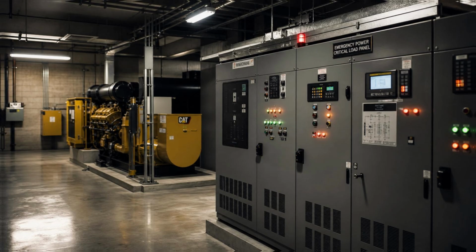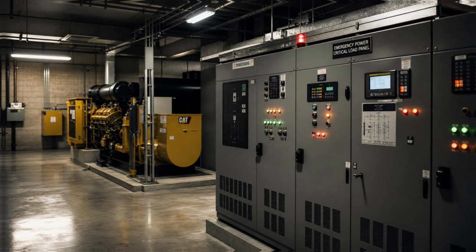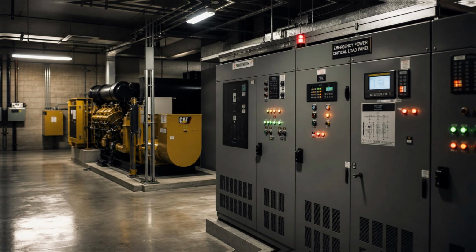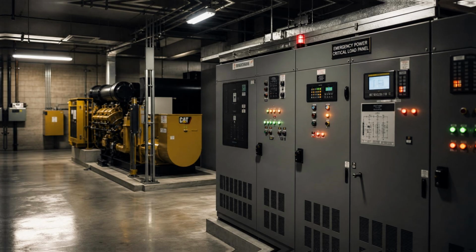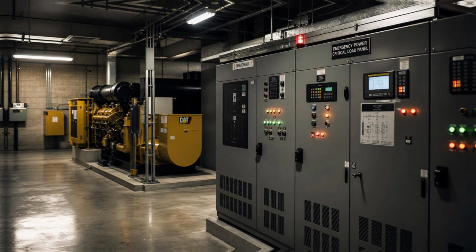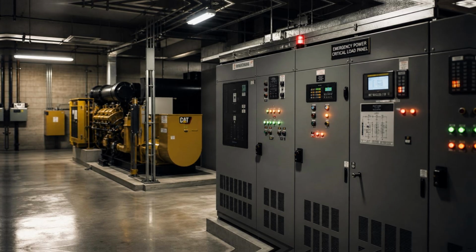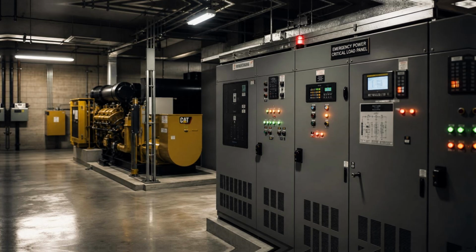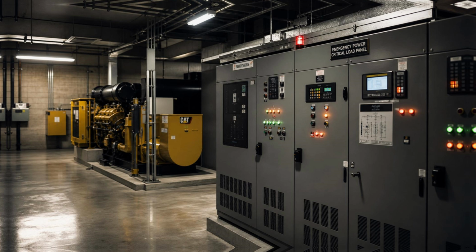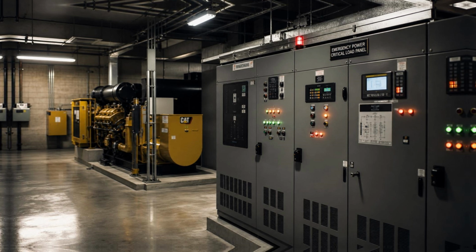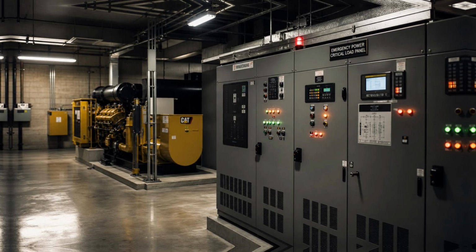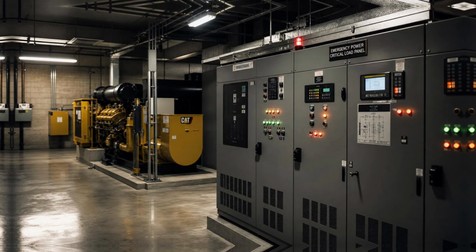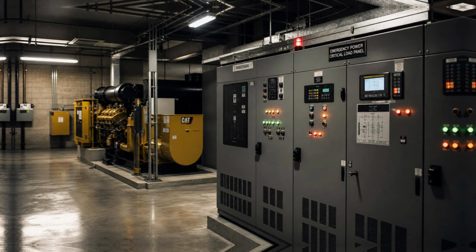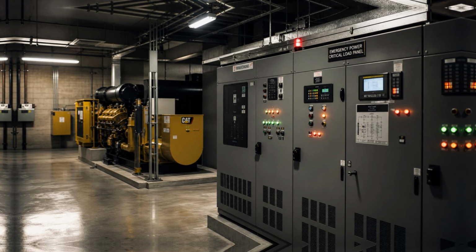The life safety branch is transferred to emergency power as quickly as the code requires, typically within 10 seconds of utility failure for hospitals, the same standard that applies to life safety systems in other building types. It is the branch that arrives first, that is most tightly time-constrained, that carries the loads on which physical safety most directly depends. And it is kept separate, not just from the normal power system, but from the other emergency branches as well. A fault on one branch must not propagate to another. The failure of a circuit feeding patient care equipment must not reach across and extinguish the exit signs. The separation that we followed in the commercial building's emergency distribution system is present here in a more elaborate and more carefully specified form.